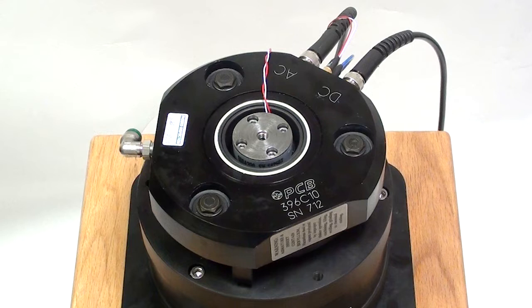To do so, we calibrate the same accelerometer in four different configurations: stud or screw mount, magnetic mount, wax mount, and grease mount. This calibration test demonstrates these effects as it is the most controllable and repeatable vibration test possible.